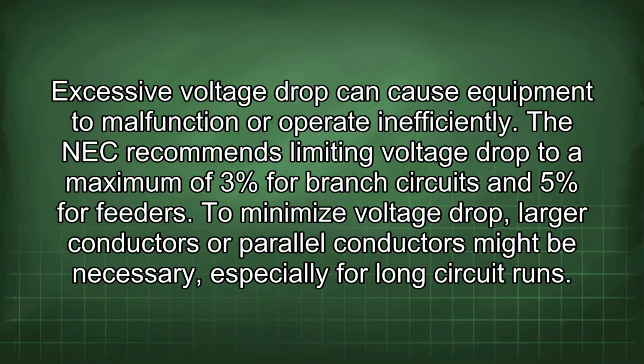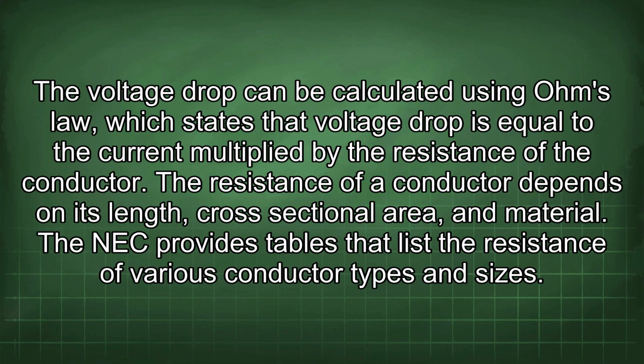The NEC recommends limiting voltage drop to a maximum of 3% for branch circuits and 5% for feeders. To minimize voltage drop, larger conductors or parallel conductors might be necessary, especially for long circuit runs. The voltage drop can be calculated using Ohm's law, which states that voltage drop is equal to the current multiplied by the resistance of the conductor. The resistance of a conductor depends on its length, cross-sectional area, and material. The NEC provides tables that list the resistance of various conductor types and sizes.